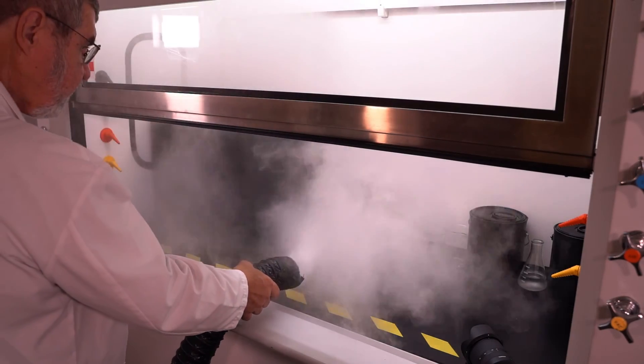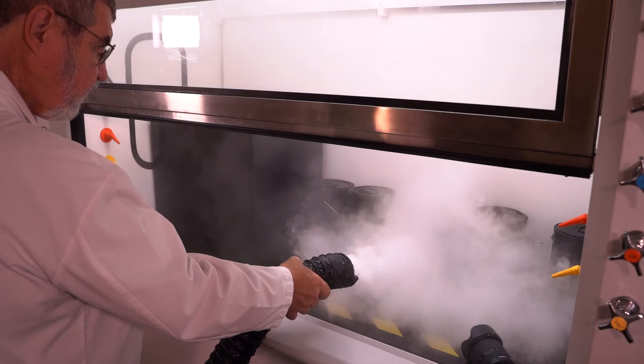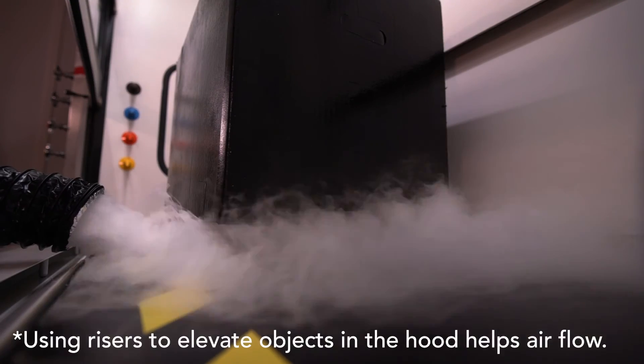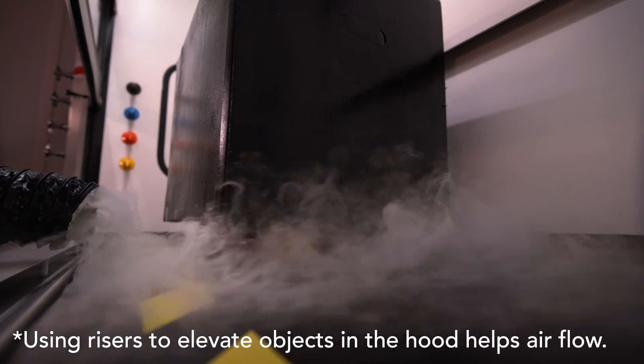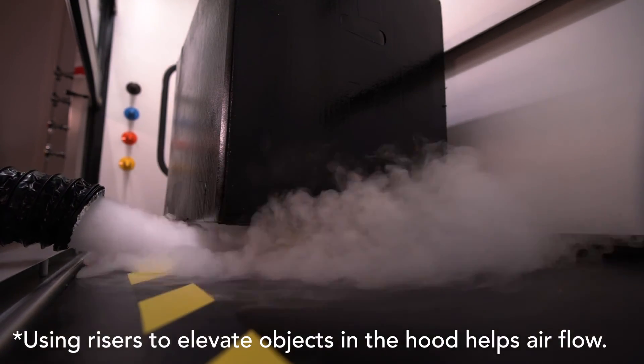As a user, there are things you can do to improve performance: don't block the baffle openings, keep objects away from the sidewalls, and elevate objects so they don't sit directly on the worktop — this allows the air to flow under them on its way to the baffles.